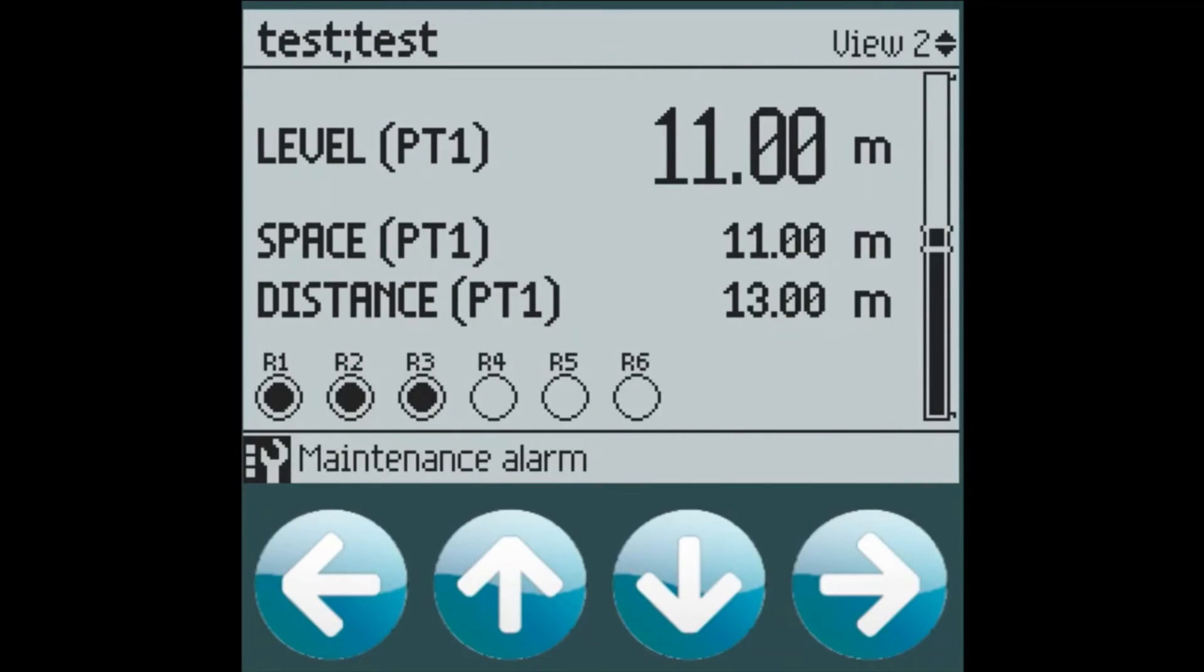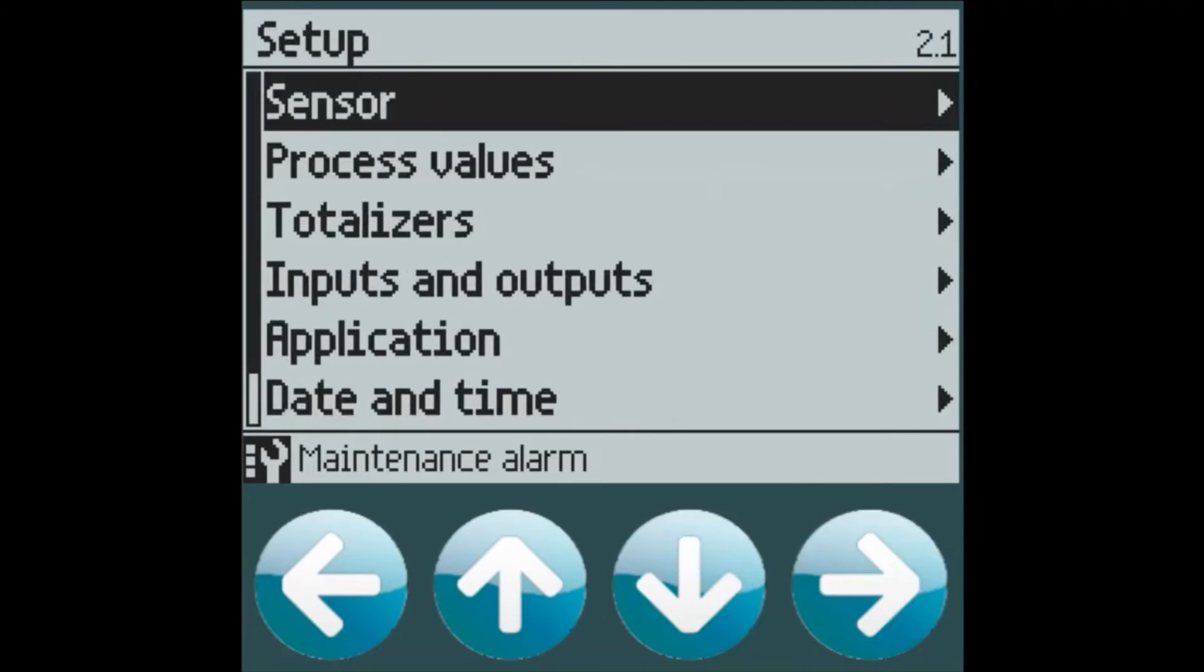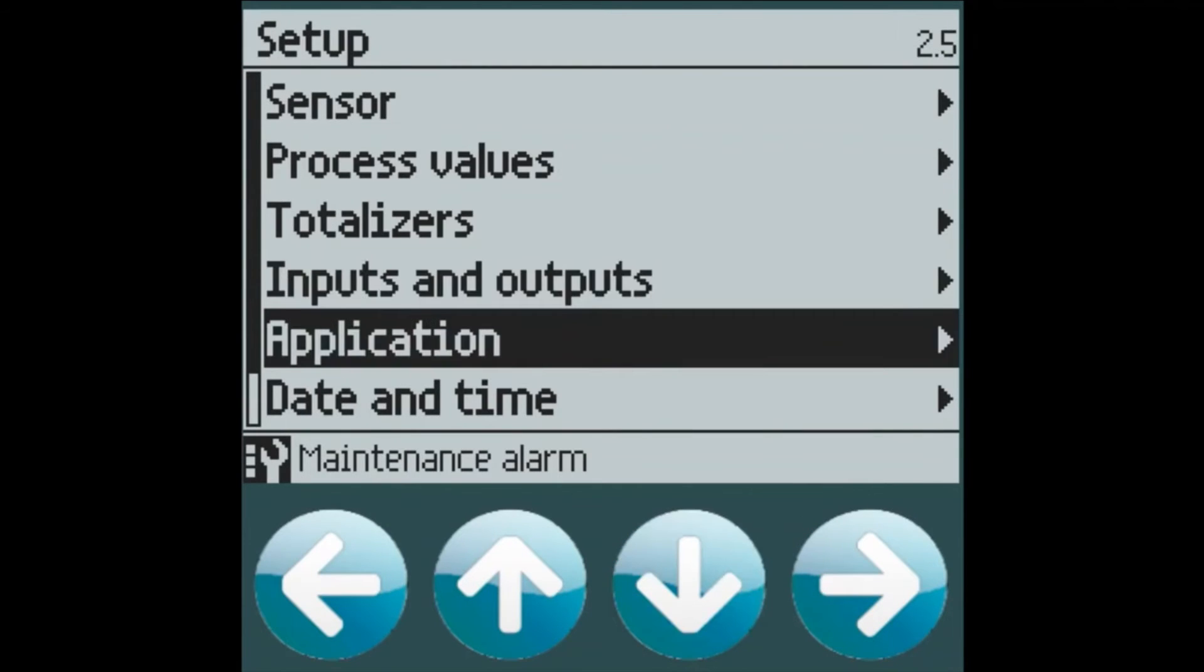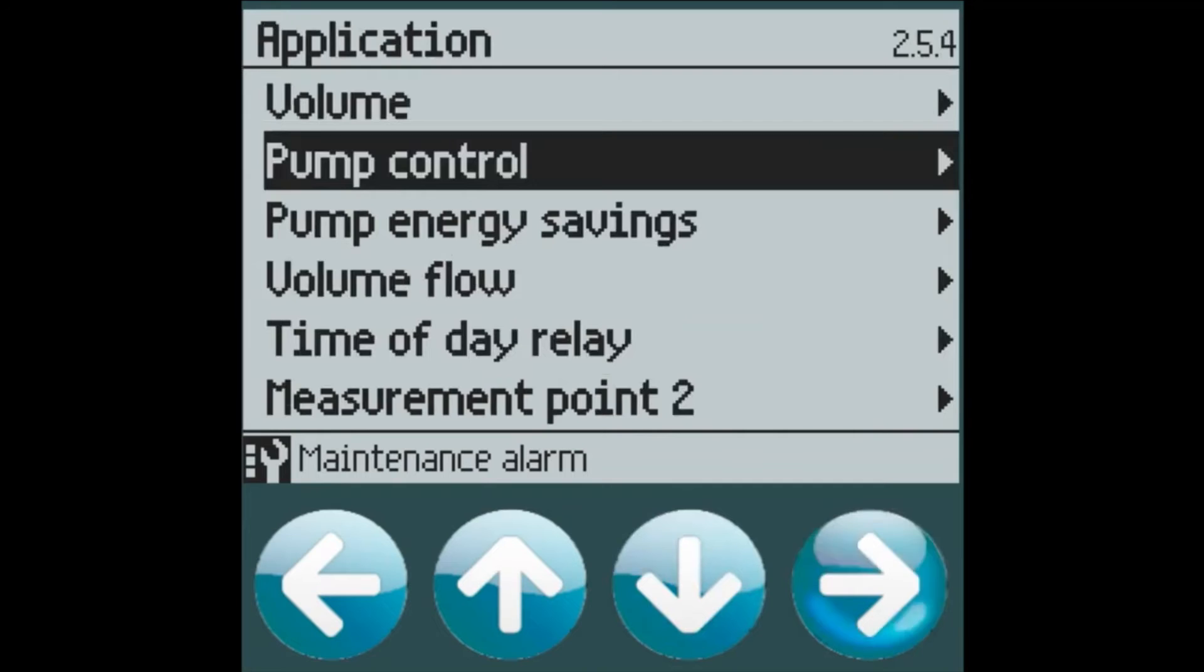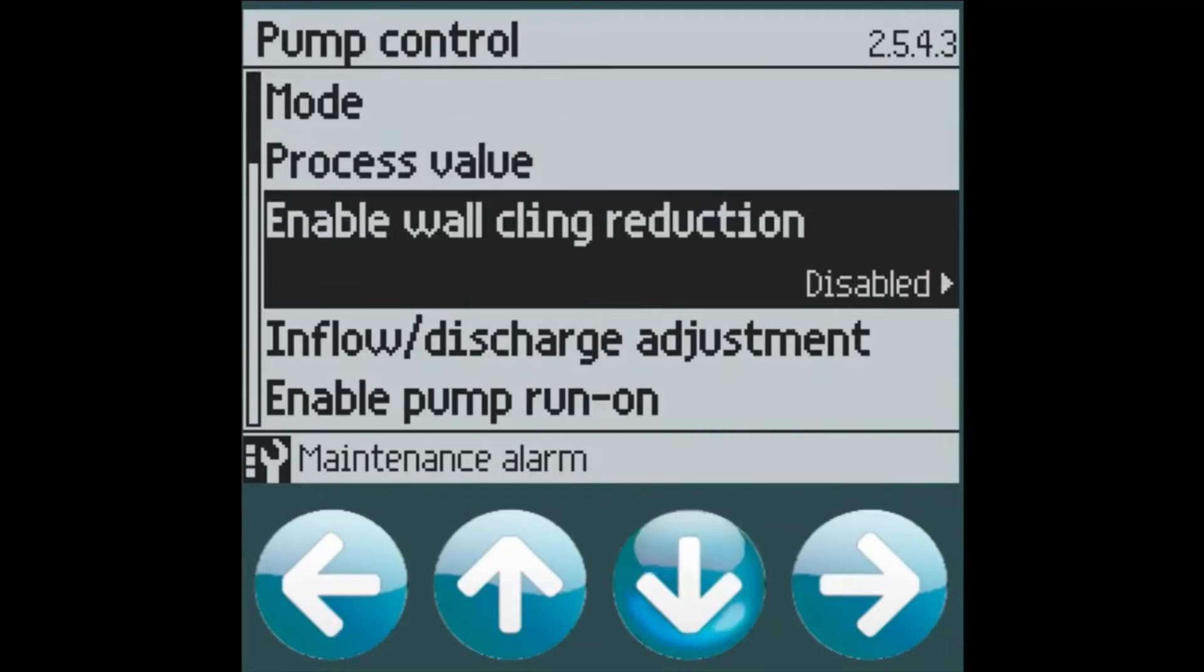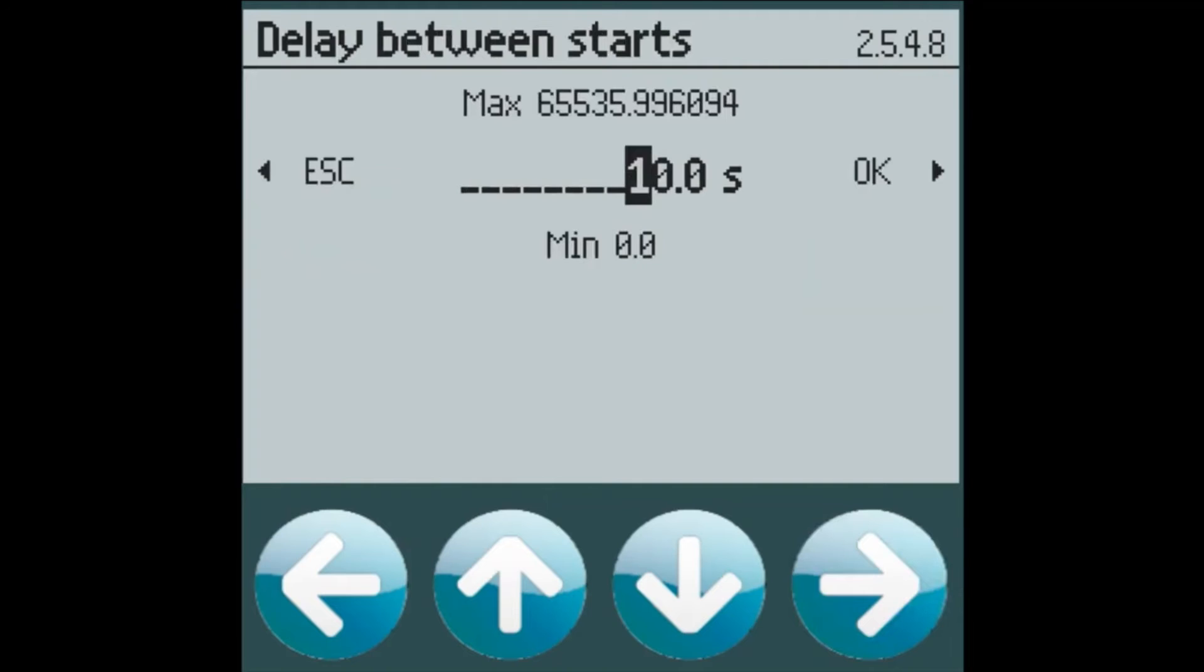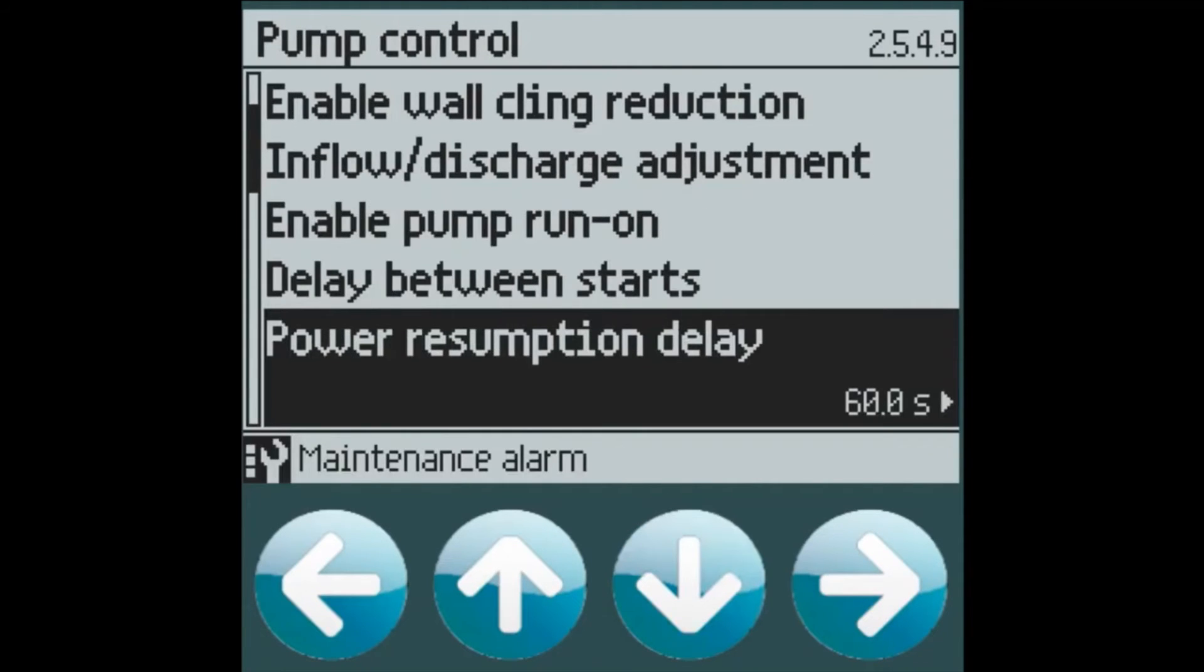The only other thing that I thought I would mention real quick is that if you're looking for advanced pump features, we have a pump control menu where you can add on modifiers like wall cling reduction, on delays, run on, inflow discharge adjustments, delay between starts on your device. For this particular application, when I'm going to show you my demo in a second, let's turn off all the delays so that the relays activate quickly in our simulation.